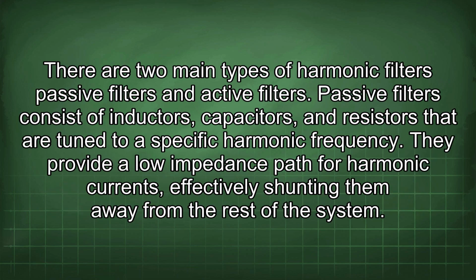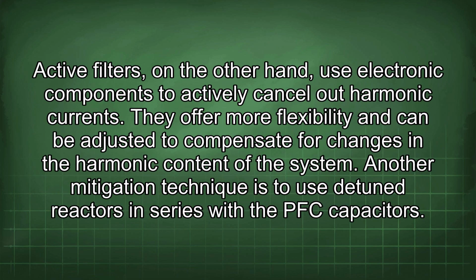There are two main types of harmonic filters: passive filters and active filters. Passive filters consist of inductors, capacitors, and resistors that are tuned to a specific harmonic frequency. They provide a low impedance path for harmonic currents, effectively shunting them away from the rest of the system. Active filters, on the other hand, use electronic components to actively cancel out harmonic currents. They offer more flexibility and can be adjusted to compensate for changes in the harmonic content of the system.